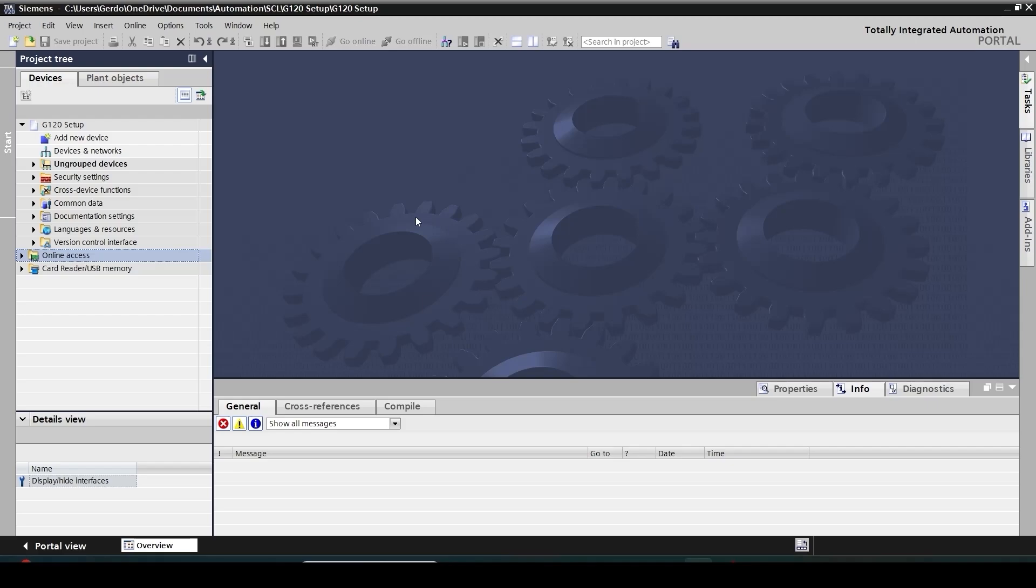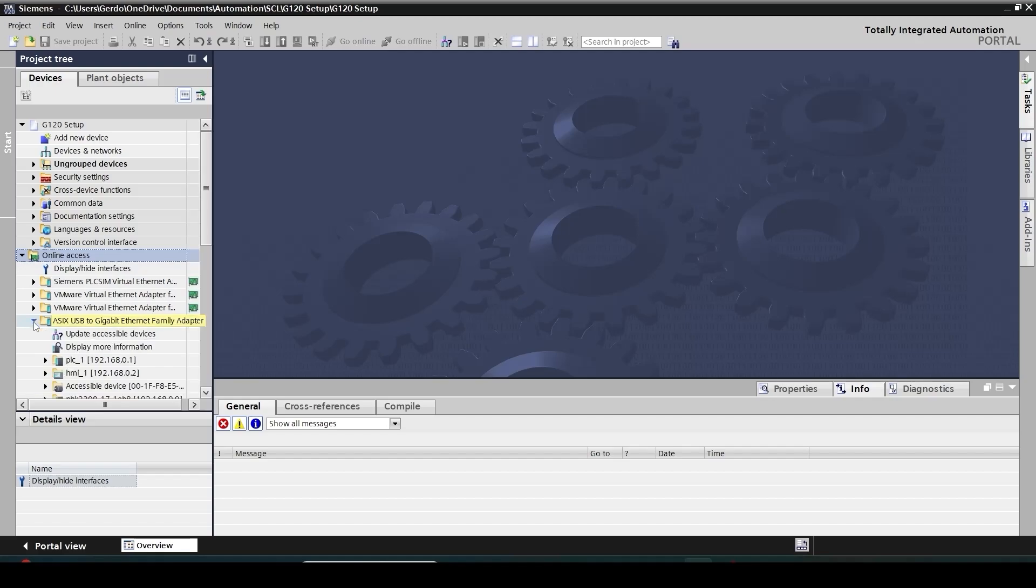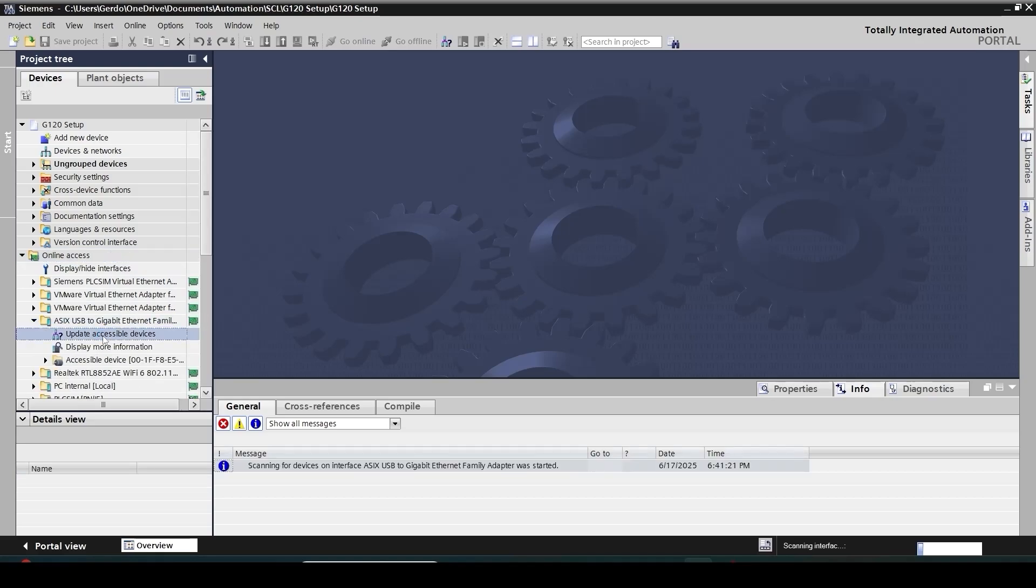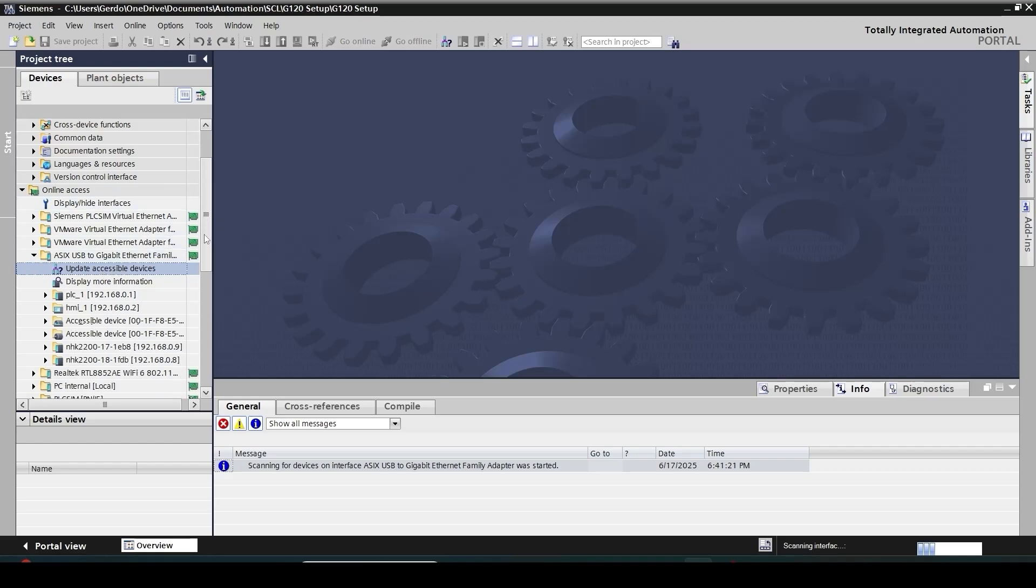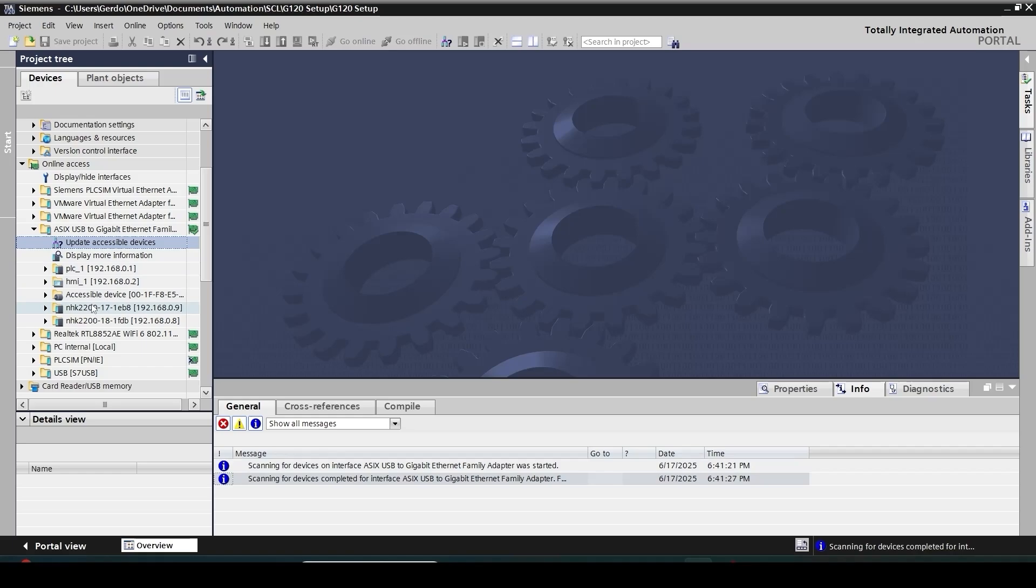First thing first, we need to ensure that TIA portal is able to scan the network and find the drive. So before adding any module I'm going to go to my online access, select my network interface card and then click on update accessible device. Depending on what you have in your system you may have PLC, HMI, and here I can see my drive which doesn't have any IP address. I can identify that with the logo of the motor on it.